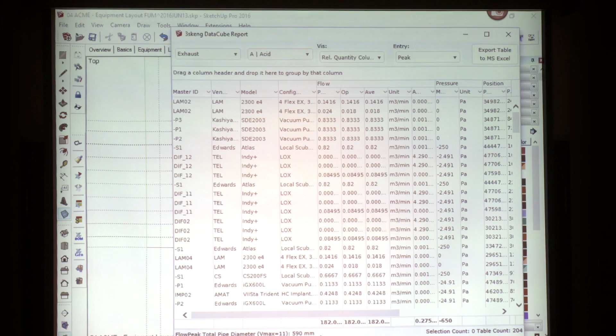We have the total sum of the acid exhaust, and as we already saw, this table updates everything you select—in this case, all the acid exhaust in the fab. Based on what we select and our target maximum velocity, 11 meters per second in this case, this gives us a proposal for the duct size: 590 millimeters, so I'd select 600. This is the main collector for the whole fab.